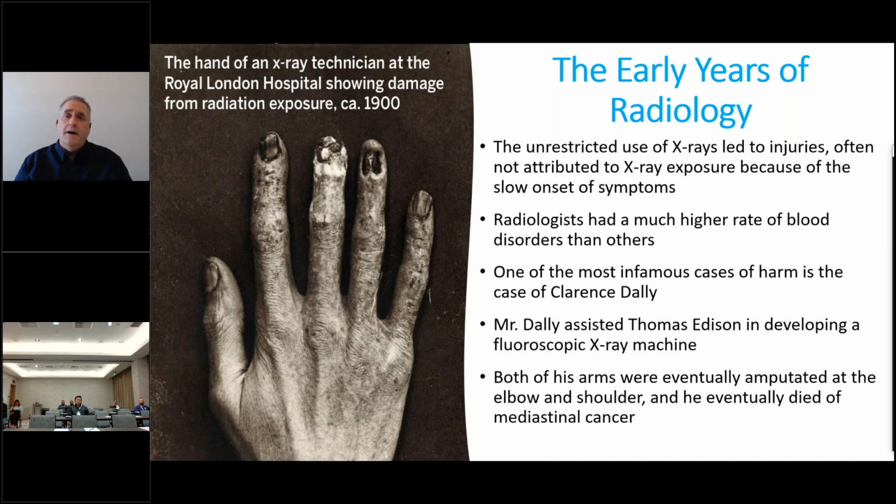So what we're doing is not just making a single quick exposure. We're turning it on and leaving it run, and we're moving the detector around to be able to see what's happening in real time. Very helpful, and we are able to deal with a lot of health related situations because of it, but inherently more dangerous. So when we work in a fluoroscopic environment, we're exposed to a lot more radiation.